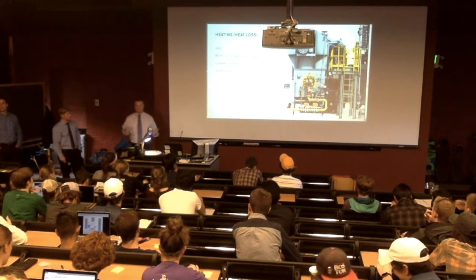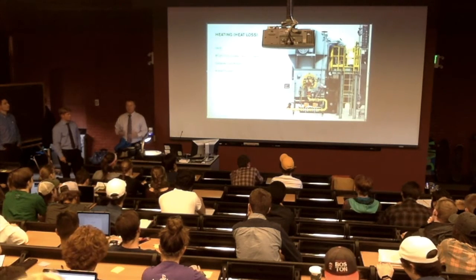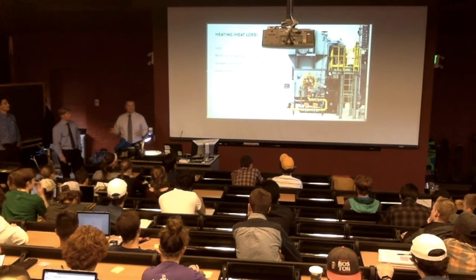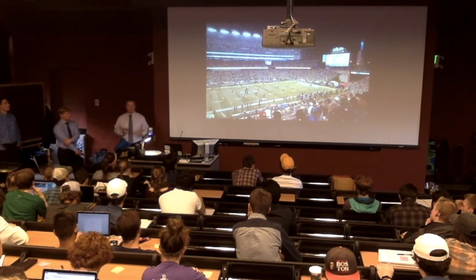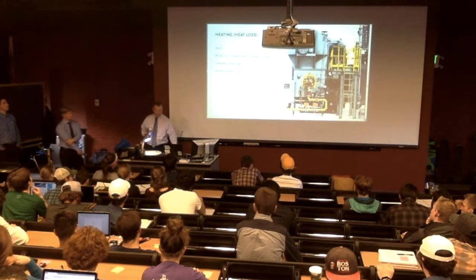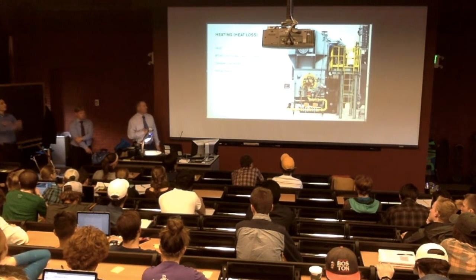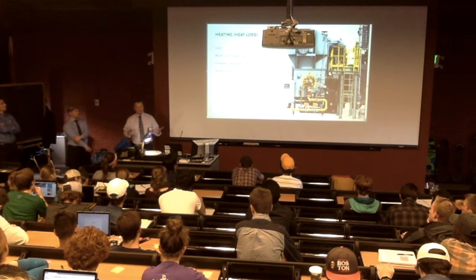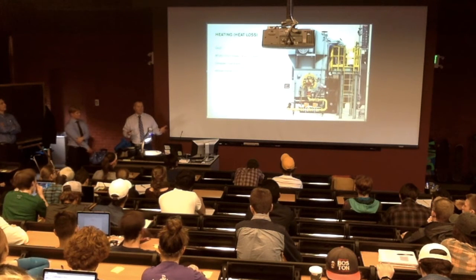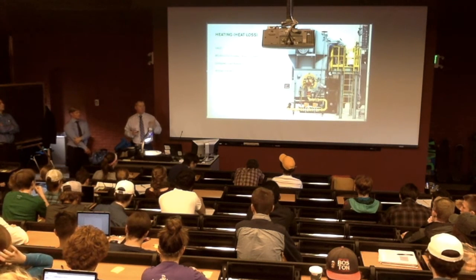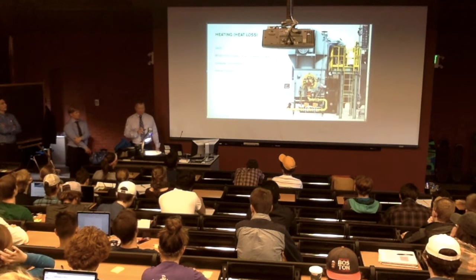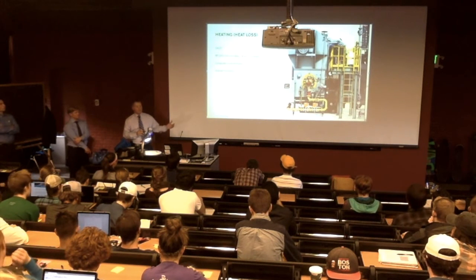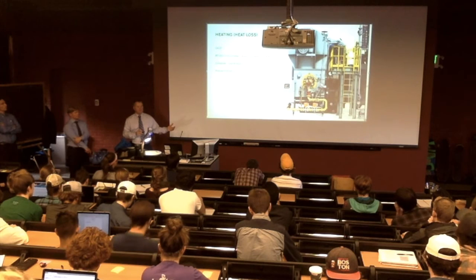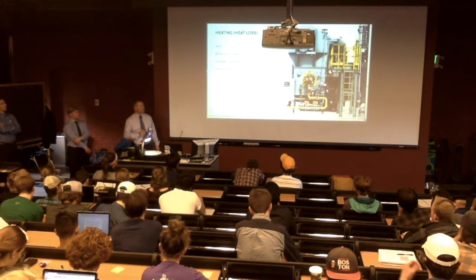You can actually use the Revit model as the baseline, so you can get all the information instead of physically going in and measuring all the different components. You can use the computer to do that for you, and it generates what the load profile or load analysis is. So each individual space in the building gets a value from that. And then from that, you can figure out what the annual operating cost for the building might be based upon the energy costs.